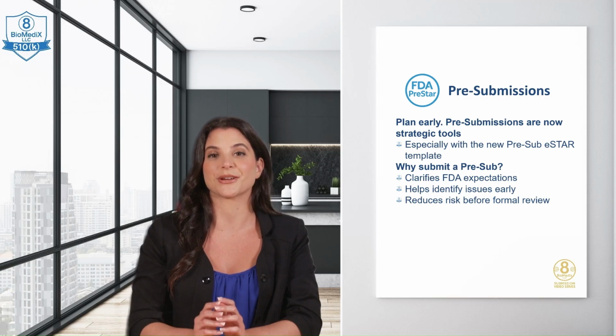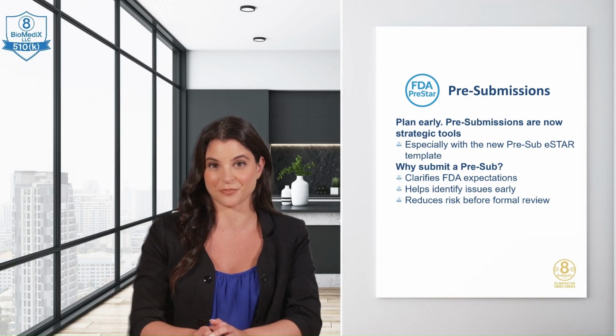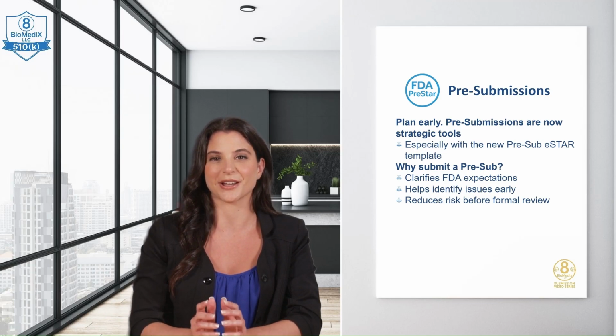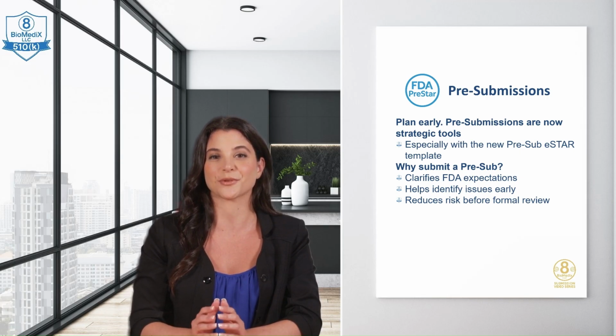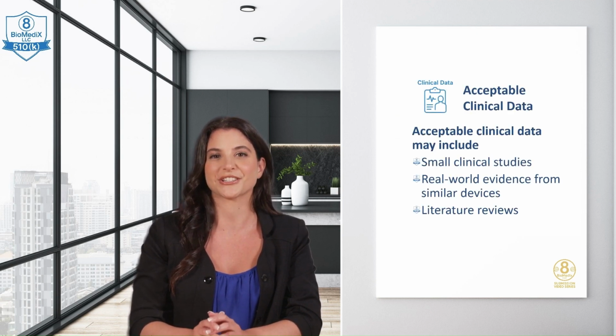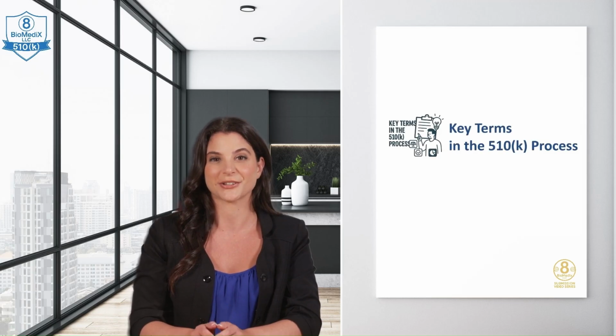Today, pre-submissions, especially using the new pre-sub eSTAR template, are not just optional, but a strategic move to de-risk your submission before entering formal review. Acceptable clinical data may include small clinical studies, literature reviews, and real-world evidence from similar devices. For example, a wearable hydration monitor using a specially designed algorithm might need clinical validation for accuracy.